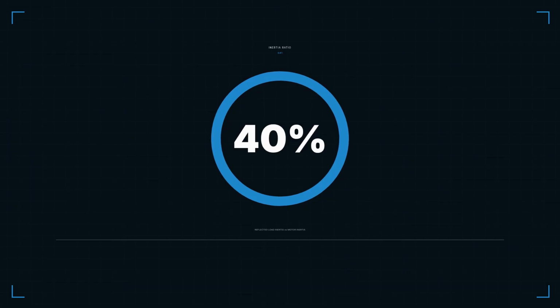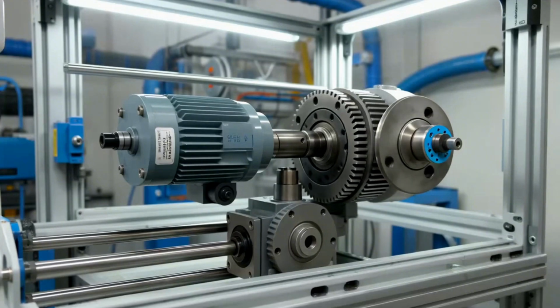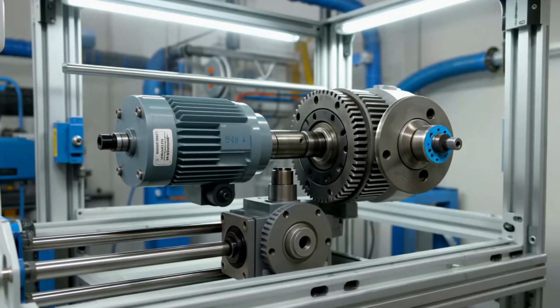The inertia ratio displays as 0.4 to 1, meaning the reflected load inertia is 40% of the motor's inertia. This ratio helps engineers determine if their motor-load combination will provide optimal dynamic performance.